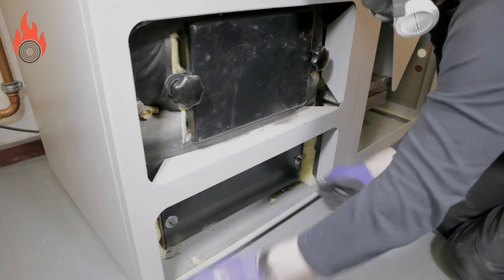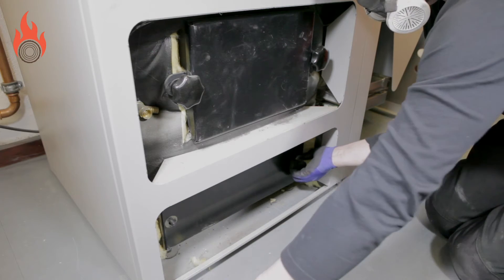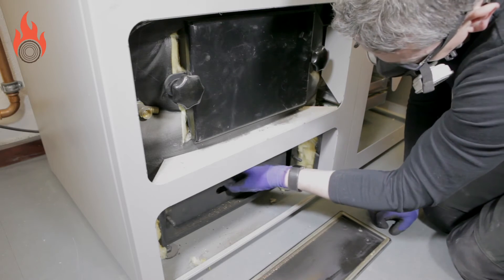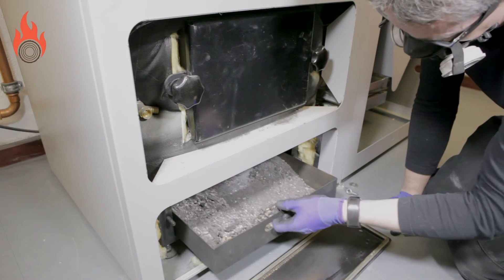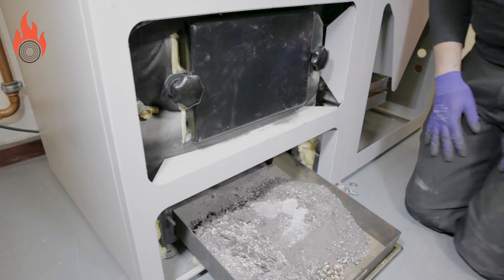In order to prevent dust escaping whilst opening the boiler door, start the flue gas fan. Open the covering door or remove front cover in order to have access to the burner cleaning door. Open the lower cleaning door to get to the ash chamber. Take out the ash drawer from the lower cleaning opening and empty it.